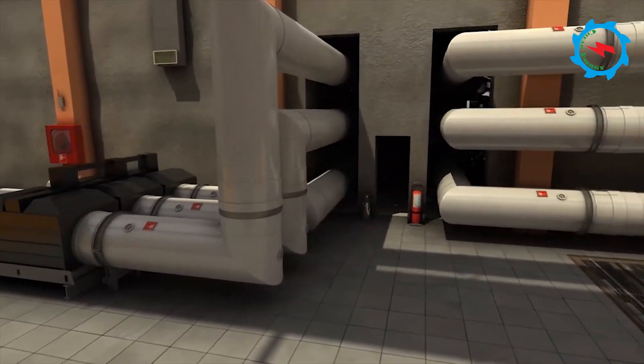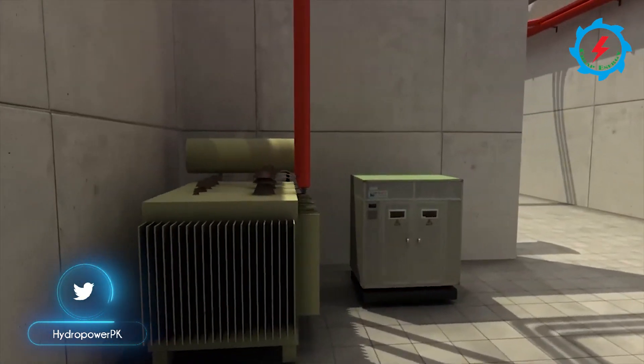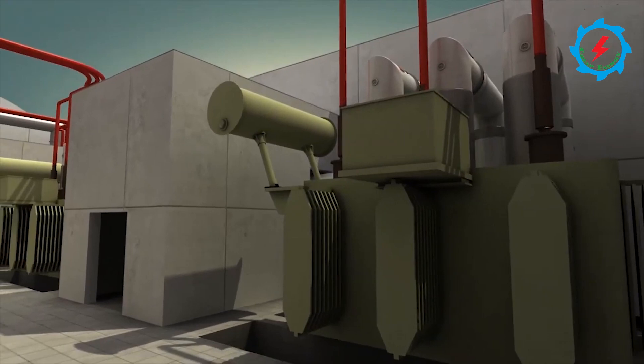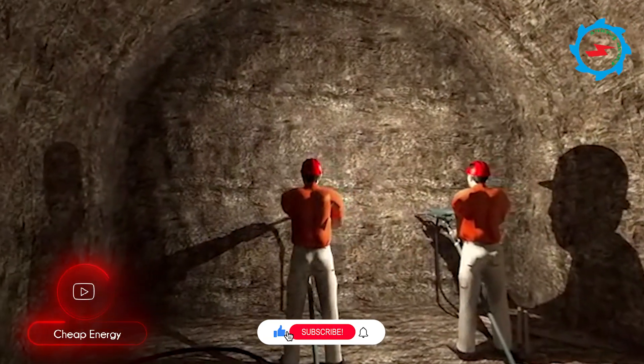The caverns are interconnected by four bus bar tunnels and one connecting passage. The transformer hall cavern lies upstream of the machine hall cavern, and it would accommodate 16 single-phase transformers. A 130-meter long access tunnel would be excavated to access the underground powerhouse. The access tunnel would be D-type, 7 meters wide and 7 meters high.